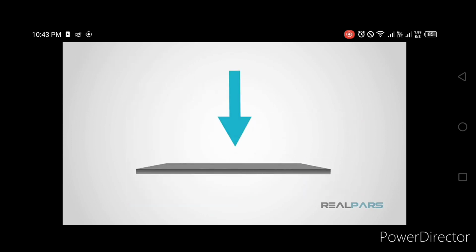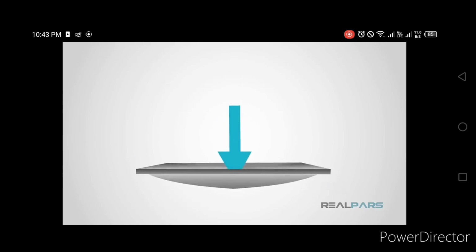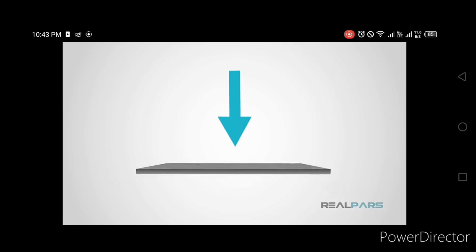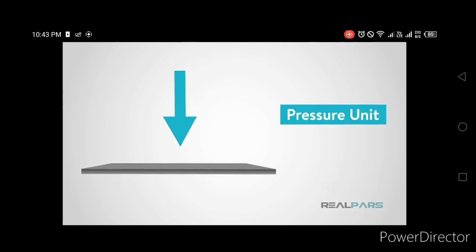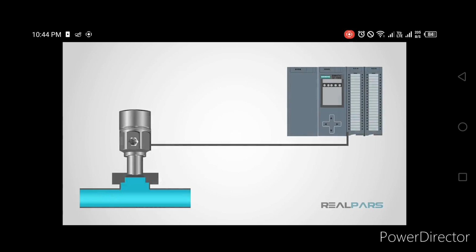Let's take a look back at what we have learned. Pressure is an expression of force exerted on a surface per unit area. The standard units are the Pascal, bar, and PSI, or pounds per square inch. Pressure sensors convert the pressure into an electrical signal that can be transmitted and displayed. This is why many sensors are referred to as transmitters.